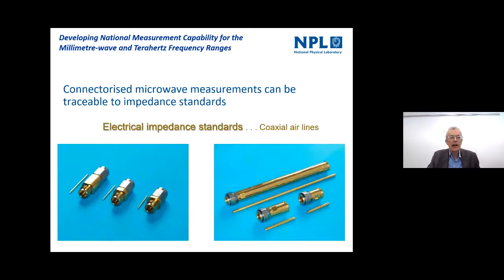And what we do is we calibrate the network analyzer using these impedance standards, which are shown in the bottom here. And basically they are reference air lines. So they're coaxial lines where the dimensions of those lines, the diameters of the center and the outer conductor, define what the impedance is of the line. And we provide that knowledge to the network analyzer so that it can be calibrated. So the network analyzer is calibrated with respect to the coaxial air lines.